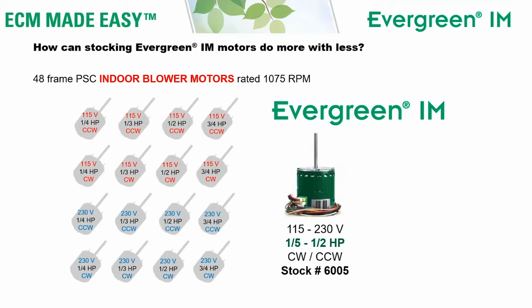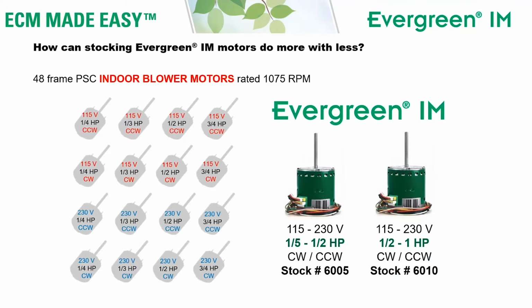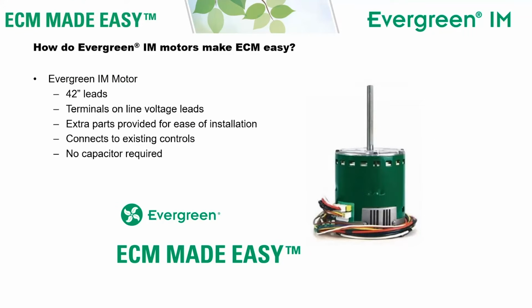Evergreen IM can replace all 16 of those ratings with just 2 motors. Stock number 6005 can replace 1/5 through 1/2 horsepower, and stock number 6010 can replace 1/2 through 1 horsepower. Both motors are dual voltage 115/230, and both motors are dual rotation. The Evergreen IM also makes ECM easy, so along with all that versatility, we've made it easy to install this motor. It's built with 42-inch leads.